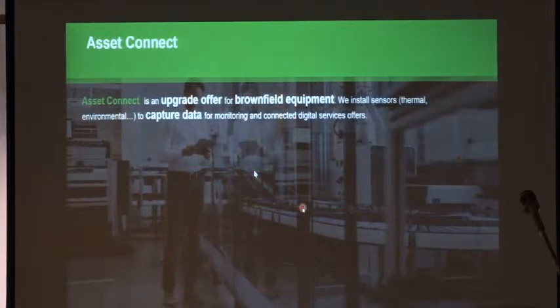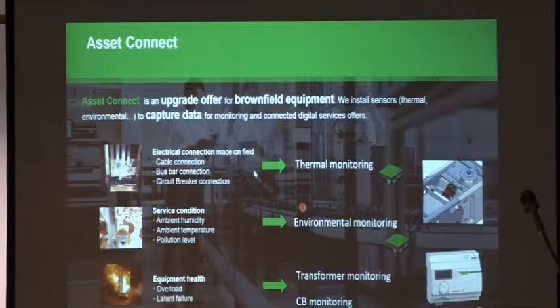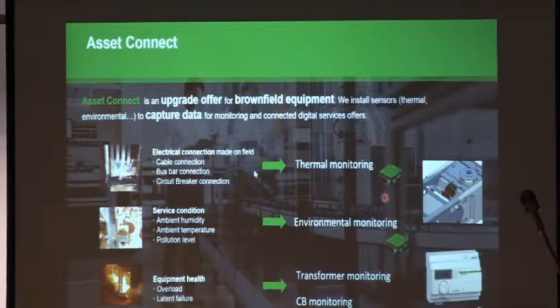In Asset Connect, part of the first stage, we can add sensors to all the assets. For example, we have different sensors like thermal sensors, which we can connect directly to bus bars, transformer connections, and breaker connections, whether medium voltage or low voltage circuit breakers. The idea is to capture, even in each phase of the breaker, the real thermal condition of that part of the connection.